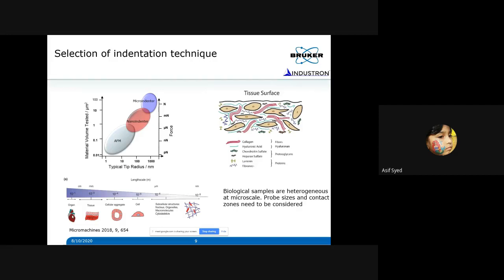For example, in Nanoindenter, you can have a micron size probe. At the same time, you can also have a nanometer scale probe, like a 30, 40 nanometer tip radius. So choosing the probe also depends upon which length scale you want to study. Do you want to study at the cellular level or tissue level or a much higher level? Okay, so that is what is important. So you have to correctly choose what type of instrument you want to use, and what is the shape and what is the size of the probe that you want to use, depending upon the material you have.